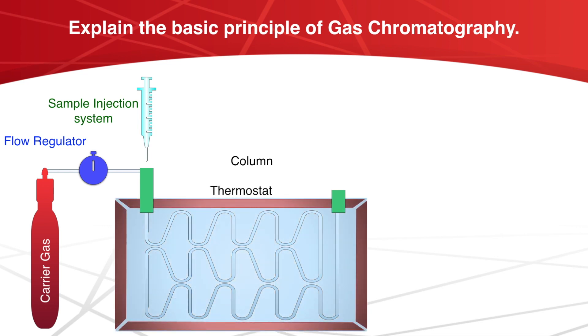And then comes thermostat. Sample injection system, column and detectors must be kept at higher temperature. The column is operated at a known constant temperature which may vary from room temperature to 623K. And this depends upon the volatility of the liquid phase.